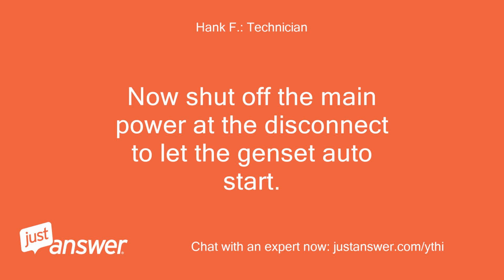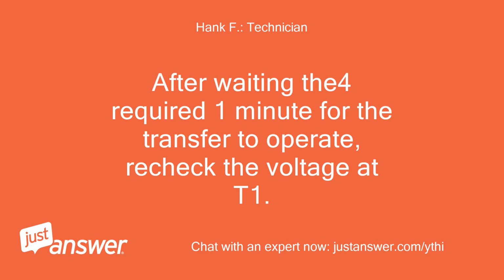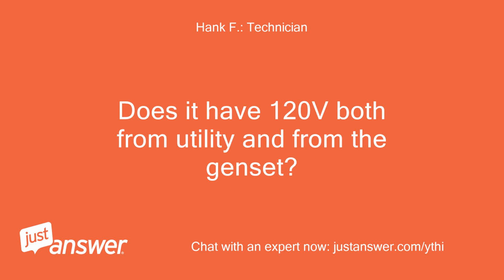Now shut off the main power at the disconnect to let the genset auto start. After waiting the required 1 minute for the transfer to operate, recheck the voltage at T1. Does it have 120 volts both from utility and from the genset?